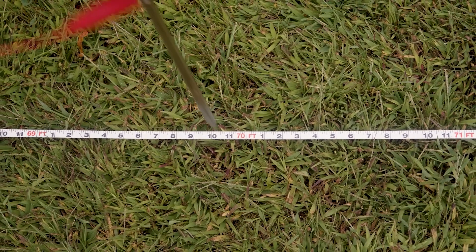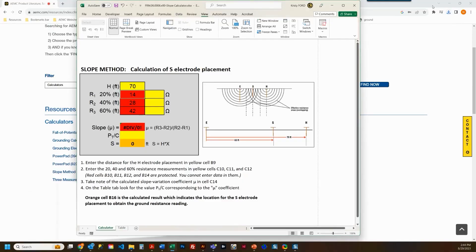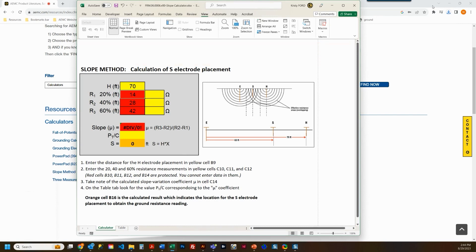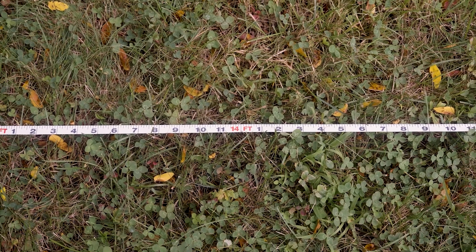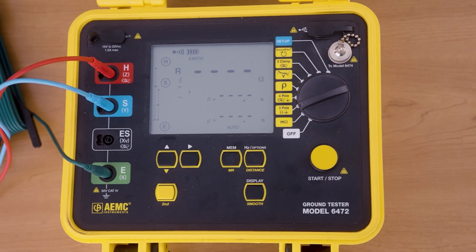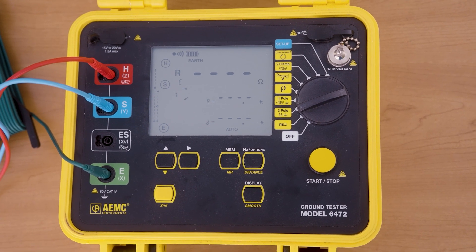We've placed our H electrode out to 70 feet. We've artificially capped the distance to remain inside the area of influence of our ground grid. Ideally, you'd go two to three times the longest diagonal of your system under test; however, place your H electrode out as far as possible. With H placed, we will now take measurements at 20, 40, and 60 percent of that H distance. These values were established by the creator of the slope method. Using the slope calculator, we will establish a slope coefficient using these three measurements. Now we are placing the S electrode to each of the three measurement points at 20, 40, and 60 percent, collecting the resistance value and entering it into the calculator.